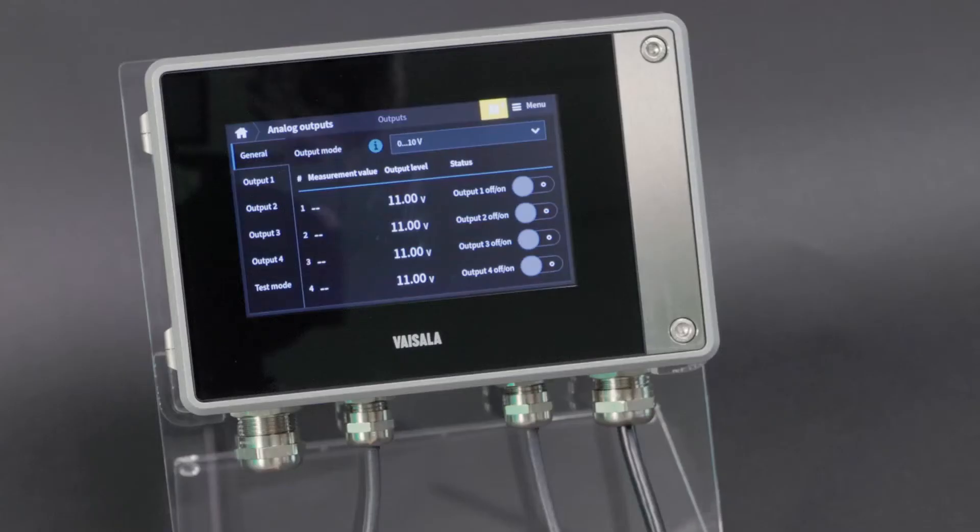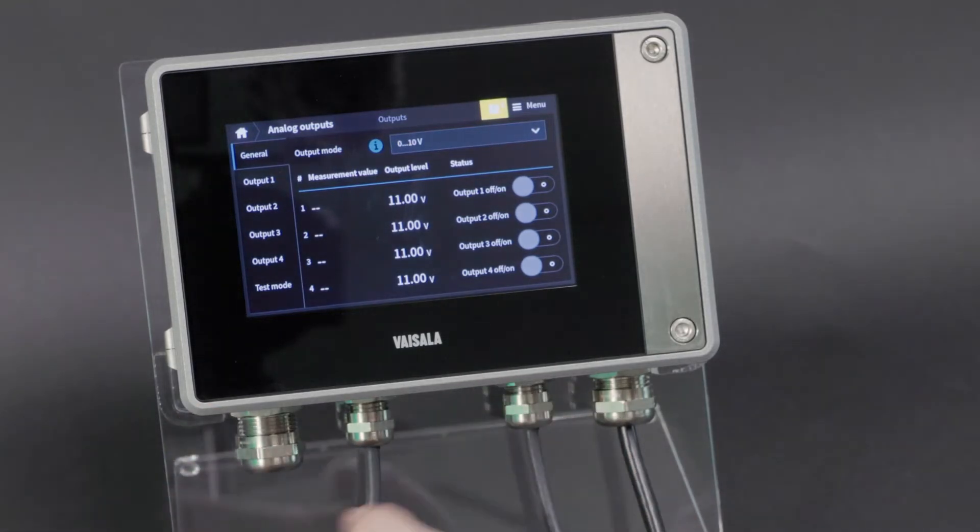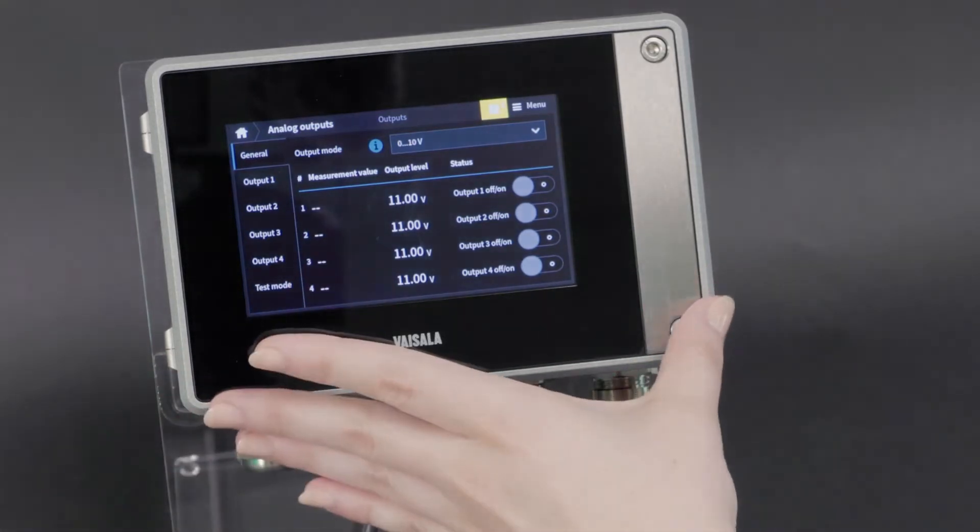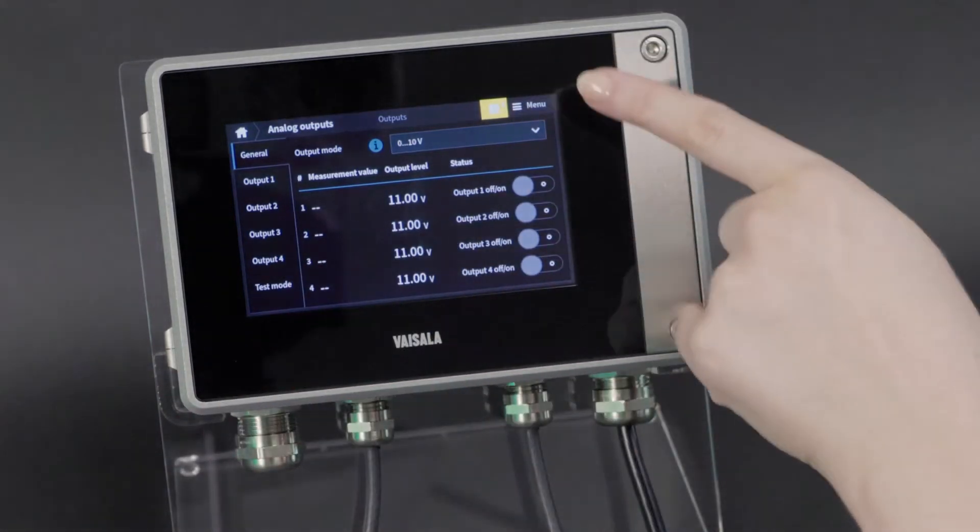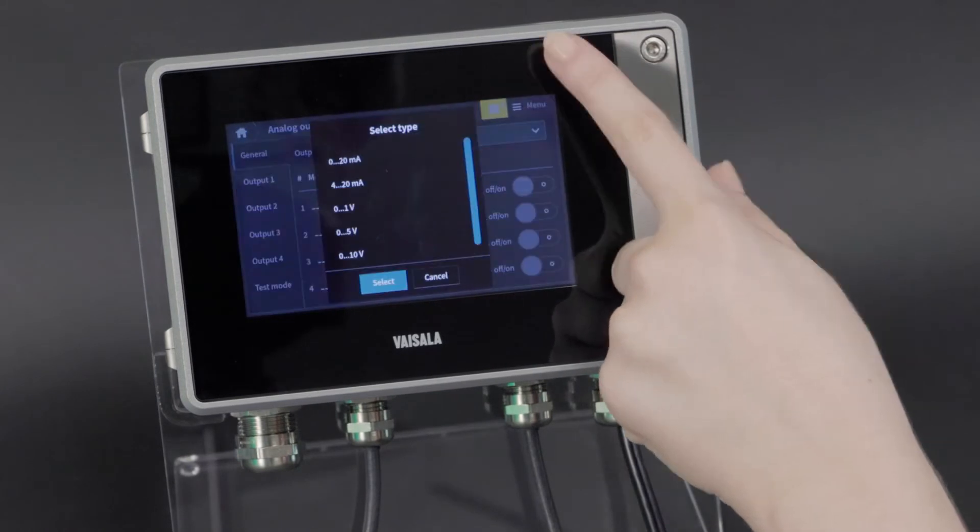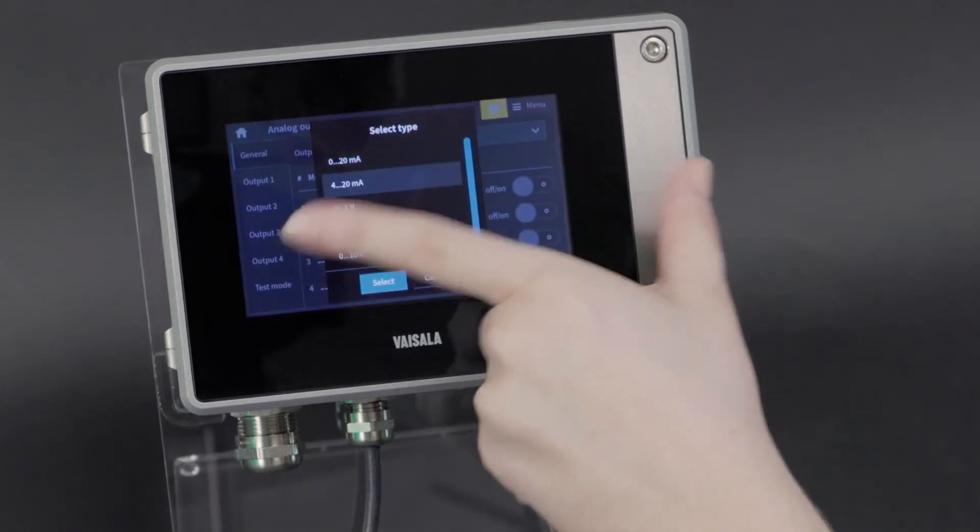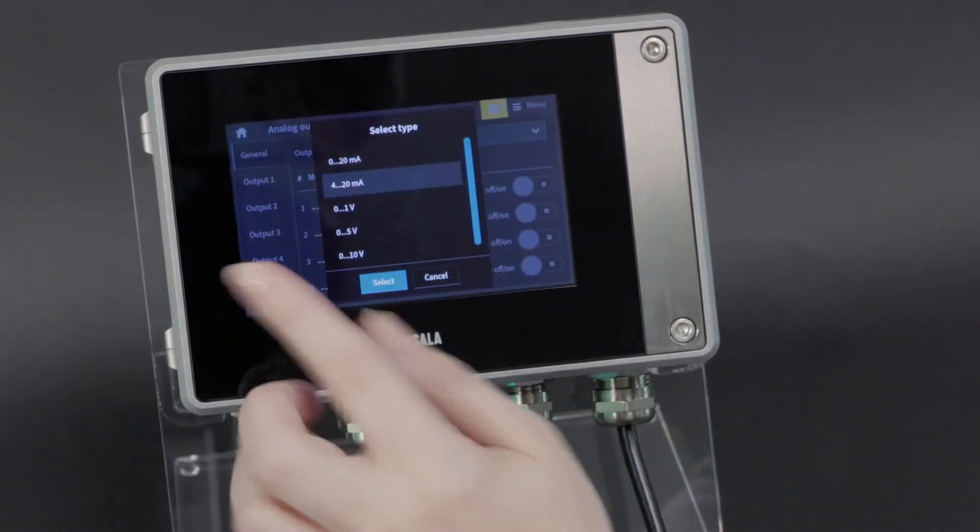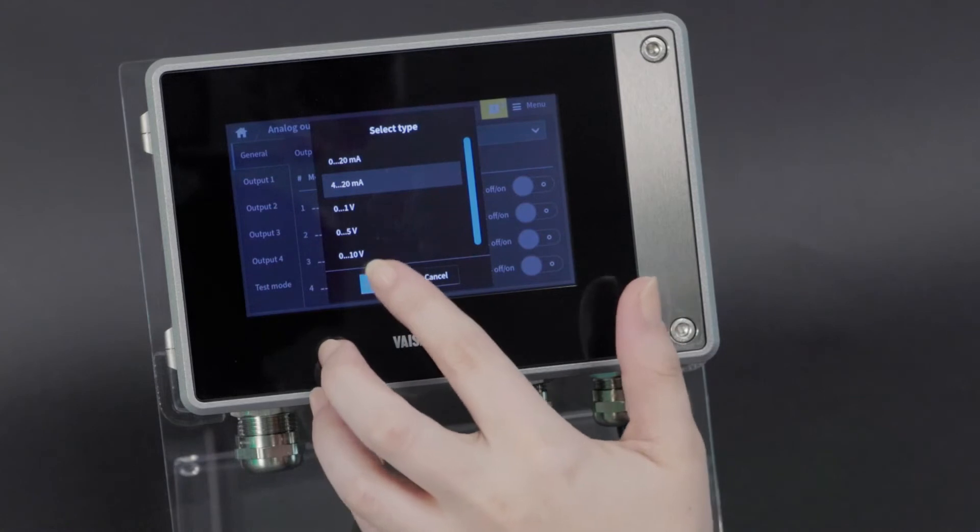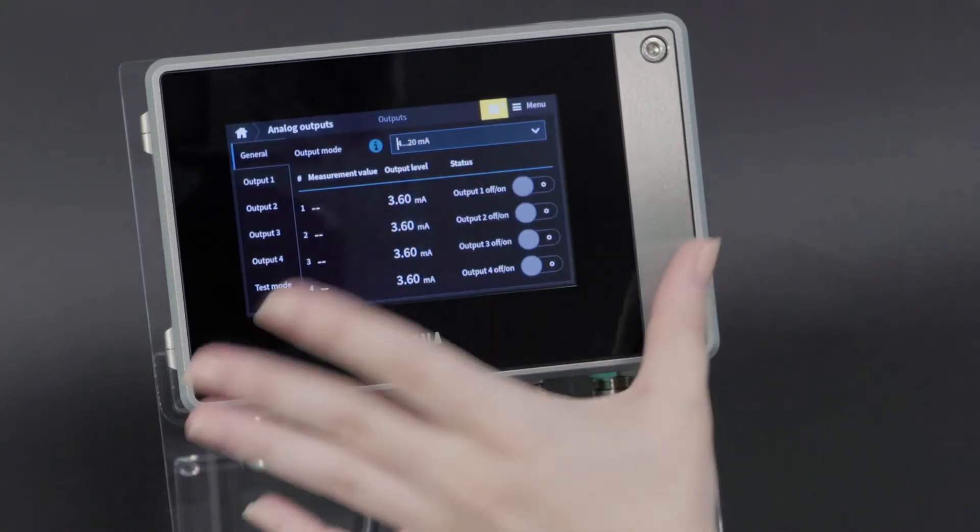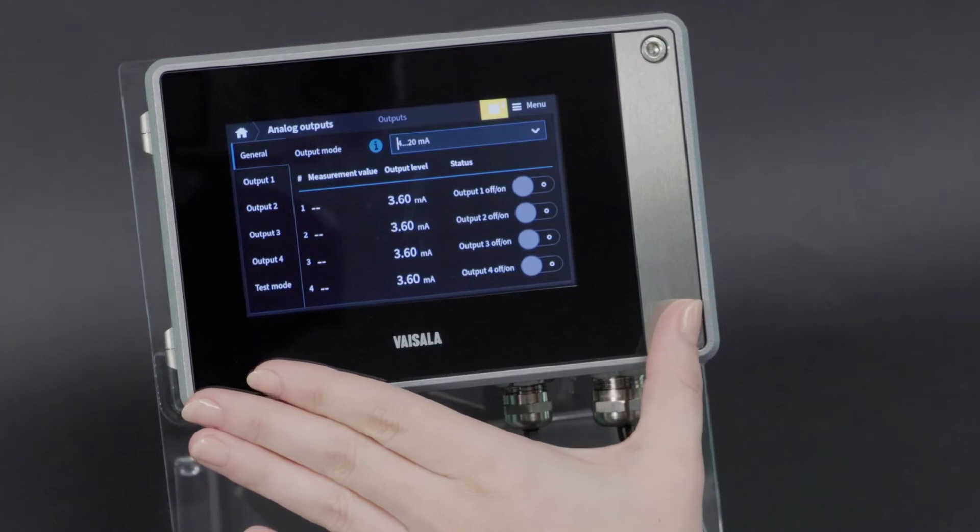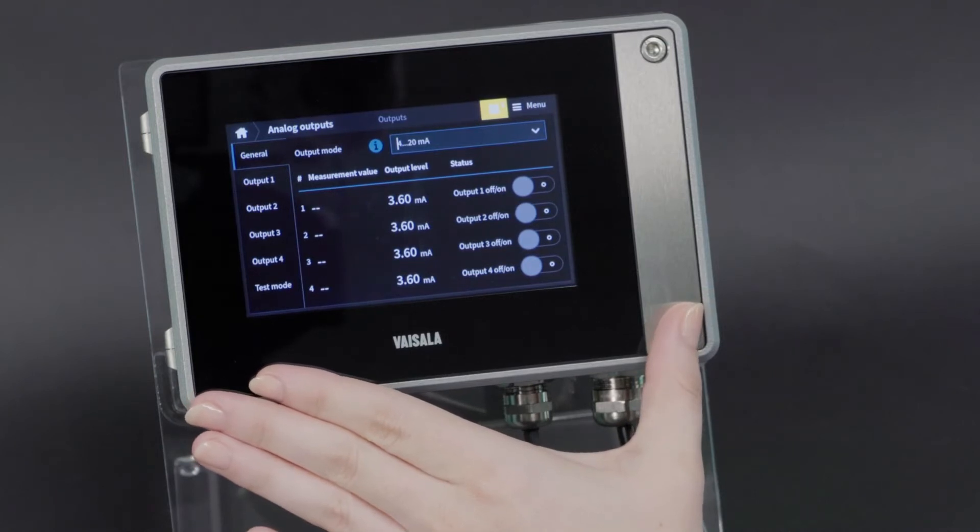The first thing you need to do when configuring your analog outputs is select your output mode. So right now it's set to 0 to 10 volts, but we can do any of these options. For example, 4 to 20 current. This output mode applies to all four outputs, whichever you configure.